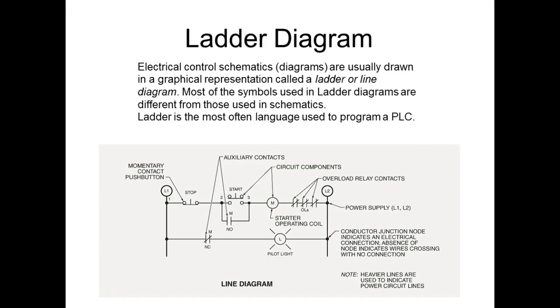These are what we call overloads. We won't have to worry about these. We would on the actual circuit itself when we wired up the motor. In the PLC, though, we don't have overloads. The problem with motors is when you start them, they pull about 6 to 8 times their run current. So if I want to start a motor and I've got an overcurrent protection device rated at 5 amps and I put a 5 amp fuse, every time I start my motor, it would do what? It'd blow, because that sucker's going to try to pull 30 amps.